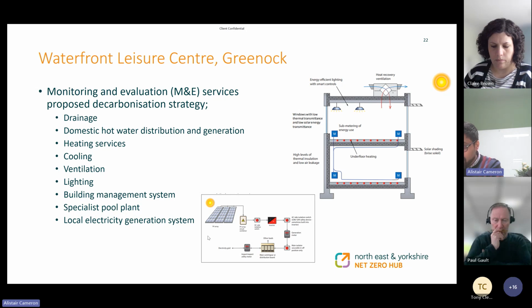That argument was further amplified by the fact that the chillers at the leisure centre have now surpassed their economic life. So the council were looking to change the chillers, and with that change in specification, and by introducing that link between the chiller plant and the heating plant, there was a great opportunity there to transfer that heat and take advantage of that kind of lower carbon heat source.